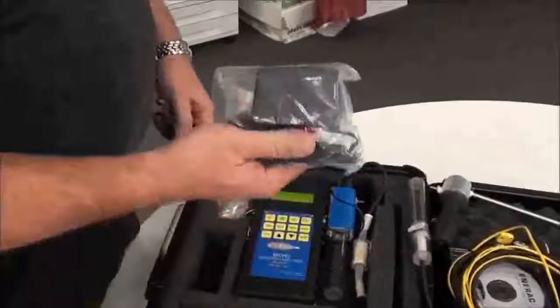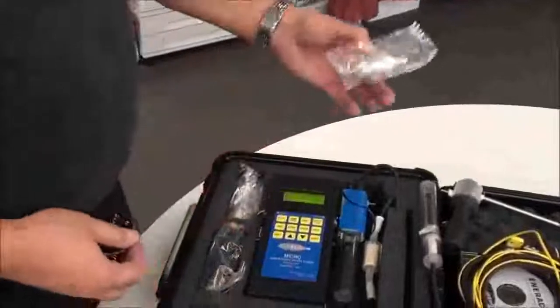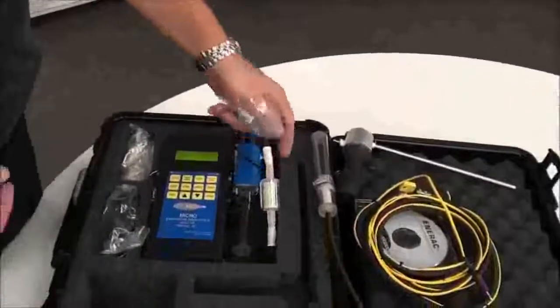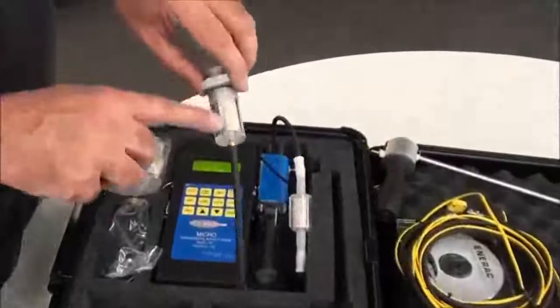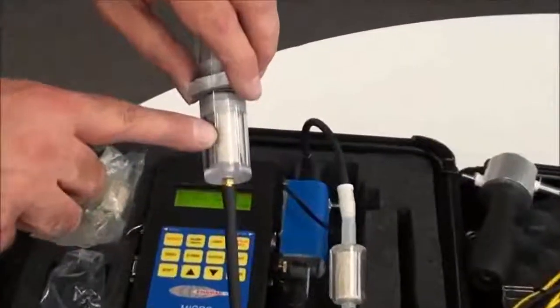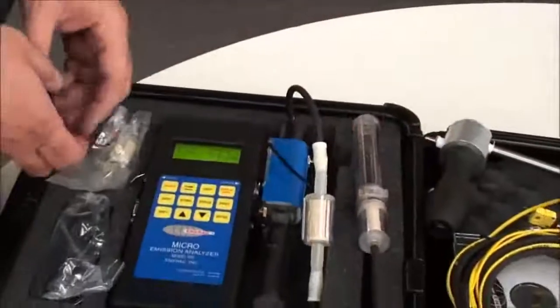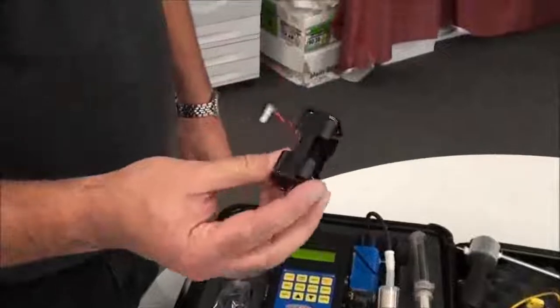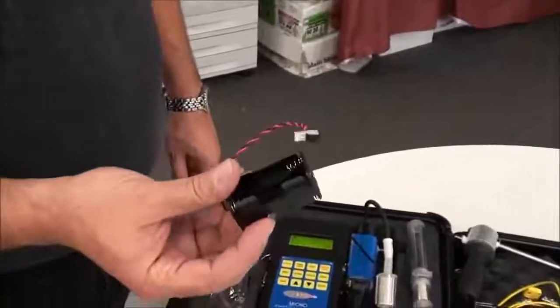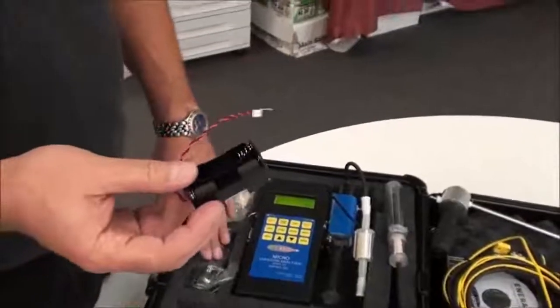In addition, you get a battery charger and an extra filter. If you have the thermoelectric cooler, you have an inline filter here. If you have the water trap, there's a fiber filter mounted inside the lower half of the water trap. You also get a 4 AA cell battery holder. If you're in the field and don't have power available to operate the unit on the rechargeable batteries, install 4 alkaline batteries into the holder, plug it in, let the unit sit for about 5 minutes so that the sensors restabilize, and then you can continue your testing.